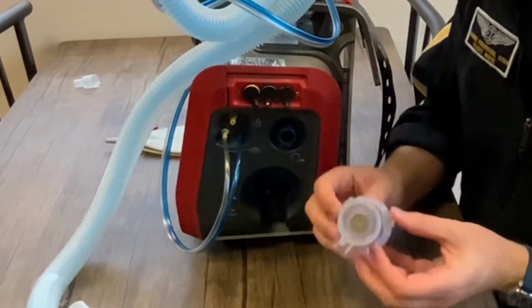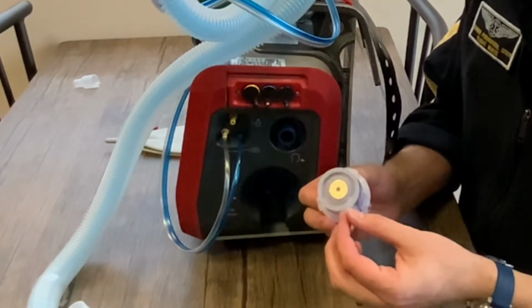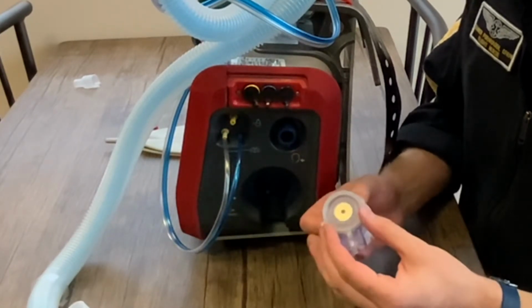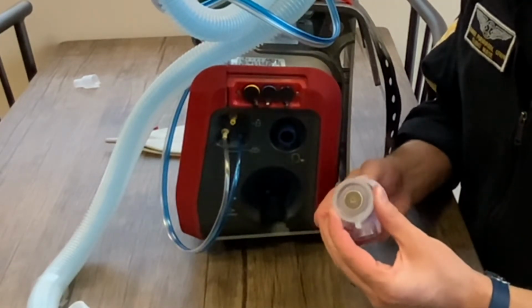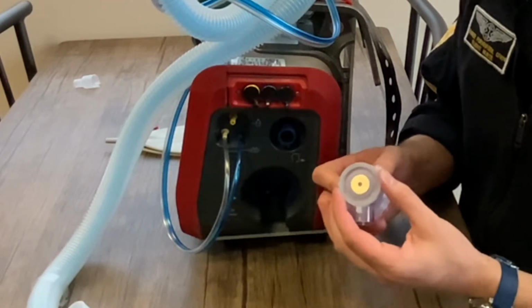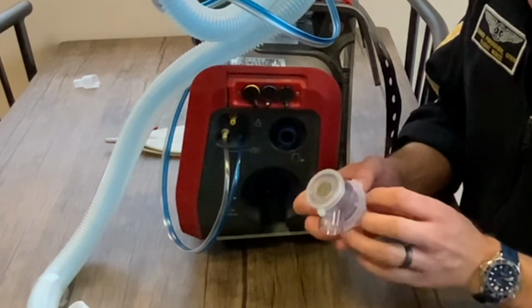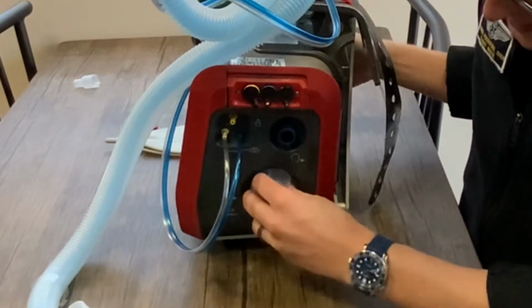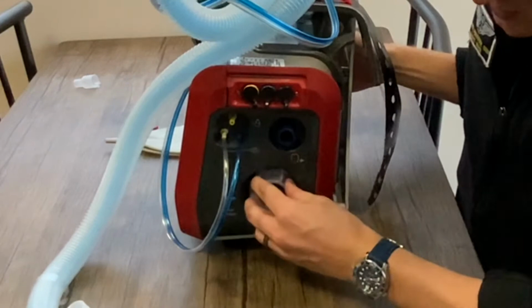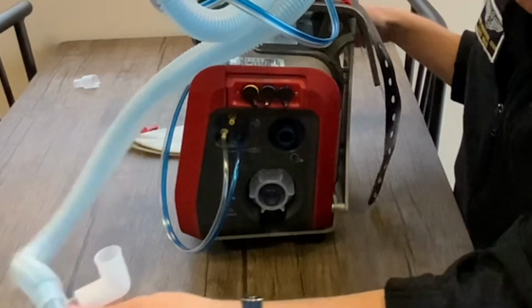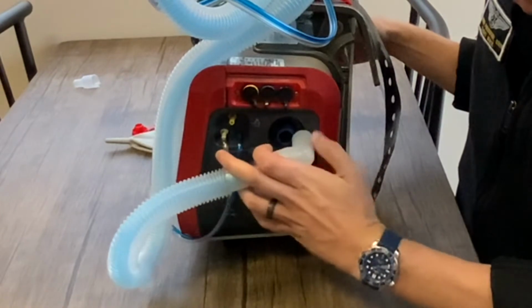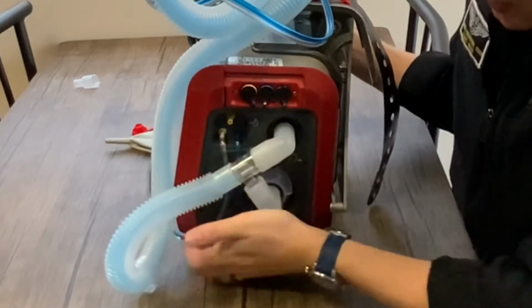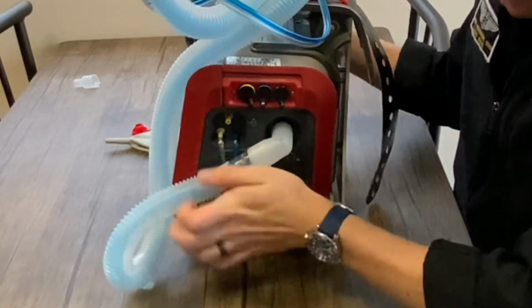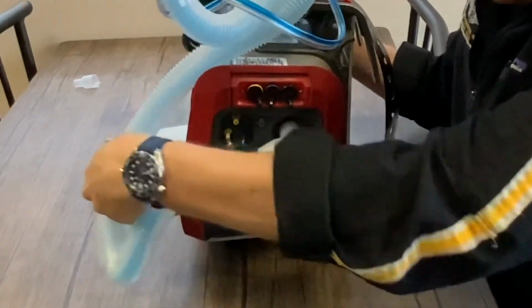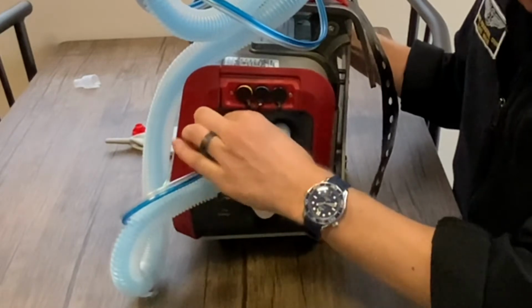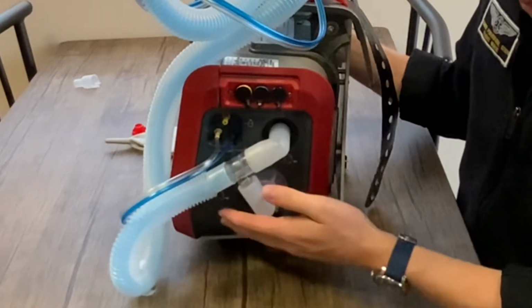To connect the tubing, start with the expiratory valve. It is imperative that the membrane is firmly seated on the valve. If you run into problems with either the flow sensor or failing the tightness check, please make sure that the membrane is on properly. This slides in, turn clockwise to lock. The tubing then slides on to the inspiratory and expiratory valves. Again, it's important to make sure these are well seated. Check your connections for blue and clear one more time, and the tubing has been connected.